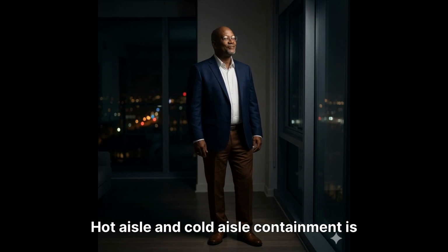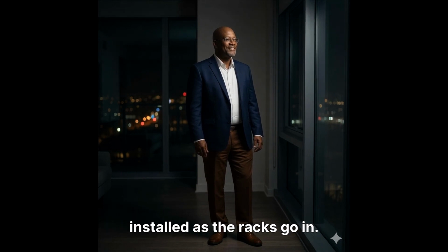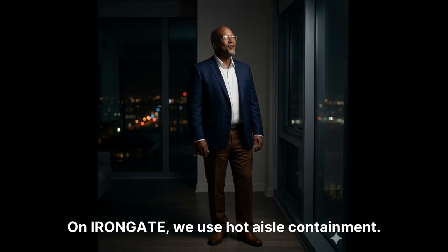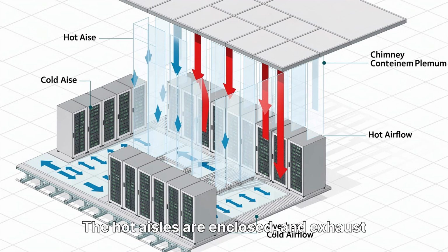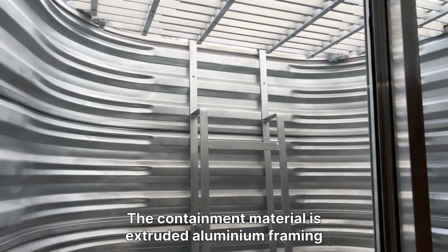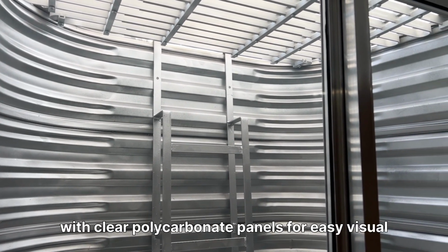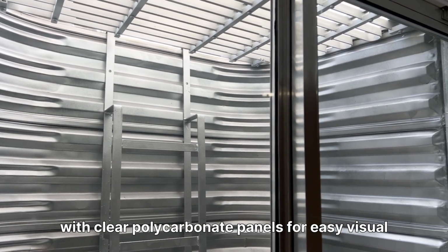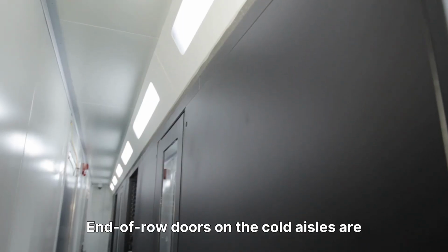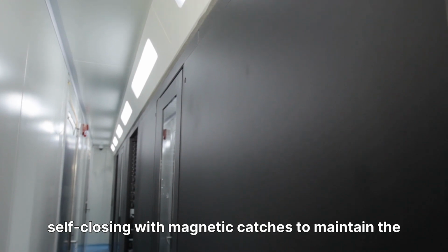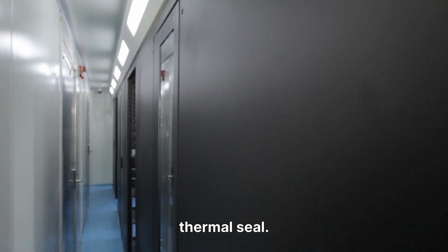Hot aisle and cold aisle containment is installed as the racks go in. On IRONGATE, we use hot aisle containment. The hot aisles are enclosed, and exhaust air is channeled directly to the CRAH return path above the ceiling. The containment material is extruded aluminium framing with clear polycarbonate panels for easy visual inspection. End-of-row doors on the cold aisles are self-closing with magnetic catches to maintain the thermal seal.